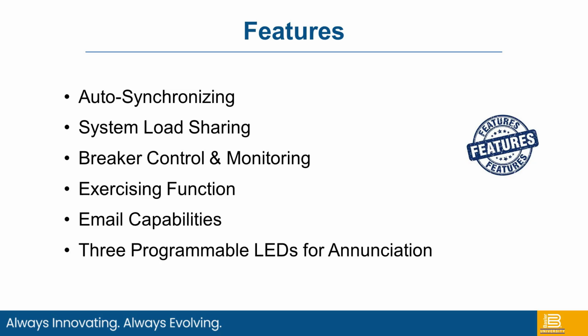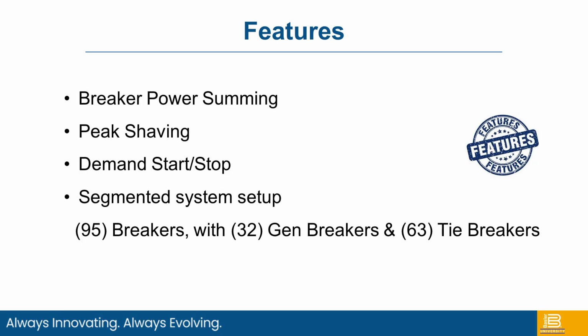So as the operator walks up to the HMI on the front screen, there's also 3 LEDs that can be programmed, and there's an Avery card that slides in behind, so you basically can print off, and it's a standard Avery card, so you can download the Avery software free, print out what you want to program those LEDs for, slide the card in, and then through BestComms program those LEDs accordingly.